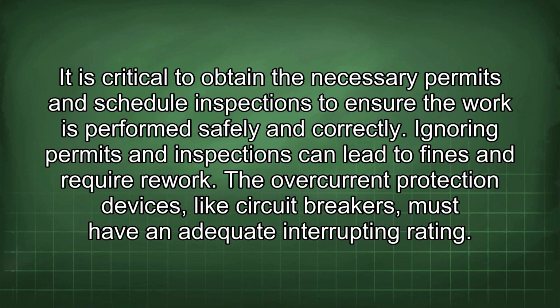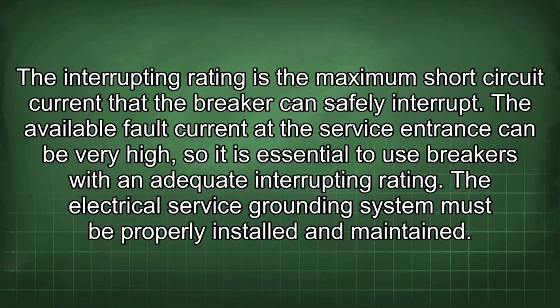The overcurrent protection devices, like circuit breakers, must have an adequate interrupting rating. The interrupting rating is the maximum short circuit current that the breaker can safely interrupt. The available fault current at the service entrance can be very high, so it is essential to use breakers with an adequate interrupting rating. The electrical service grounding system must be properly installed and maintained.